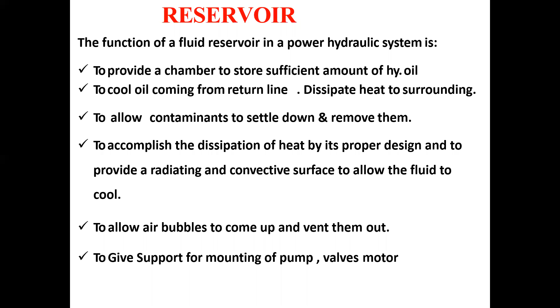Then what is a reservoir? A reservoir is a component which stores the oil of the hydraulic system. It also performs some other functions other than storing the oil. The functions are listed on your screen. You can read it here. First function is to provide a chamber to store a sufficient amount of hydraulic oil, then to cool oil coming from the return line, to allow contaminants to settle down and remove them, then to accomplish the dissipation of heat by its proper design, and to provide a radiating and convecting surface to allow the fluid to cool. Next one is to allow air bubbles to come up and vent them out, to give support for mounting of pump and valve motors. All these are the functions of the reservoir.